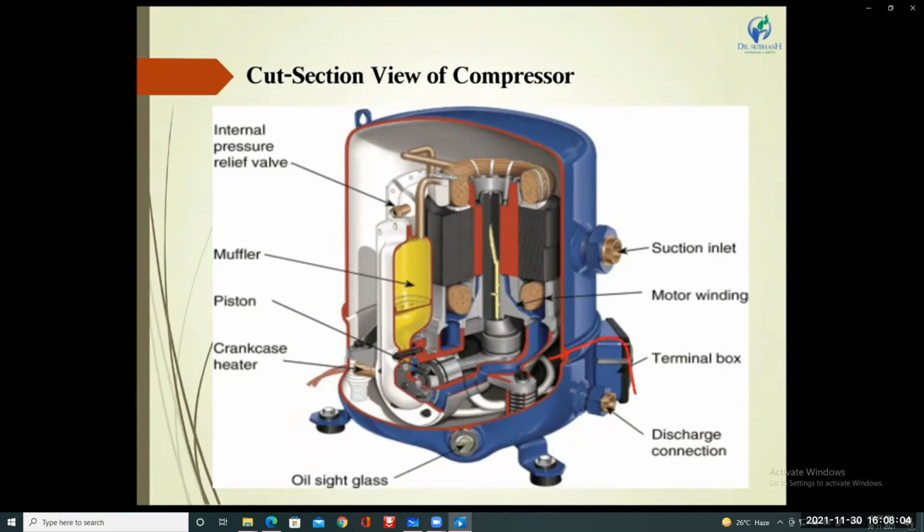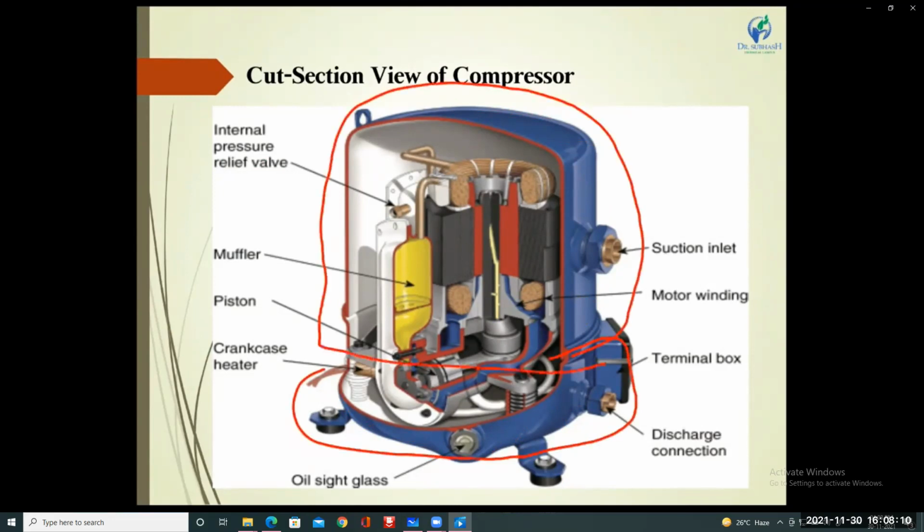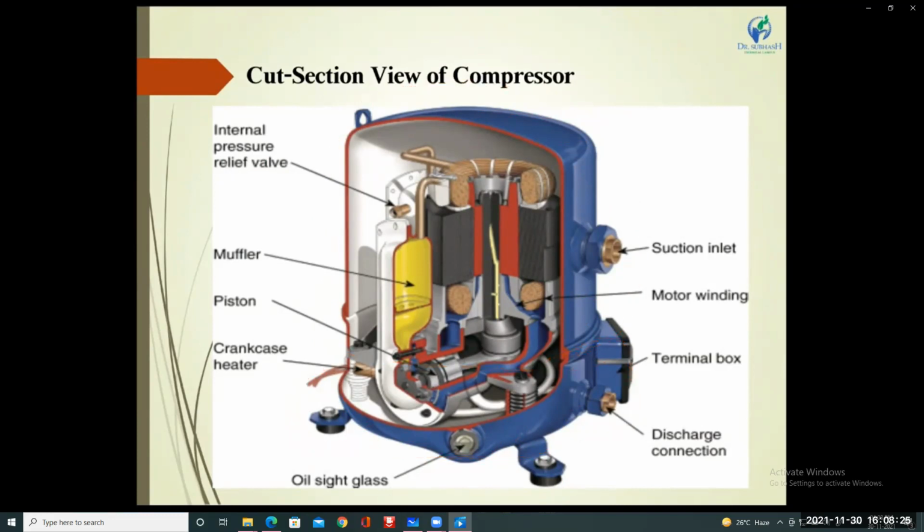A half cut section is there, and another hermetically sealed half cut section is there. The compressor is divided into two portions. The bottom half is where we mount the electric motor, and the top half is a cover for the whole assembled system, and after that we have to weld it. This portion is shown as the weld between the two portions of the compressor casing. The bottom and top casings are welded with a high-quality weld, or sealed. We have to show all the components.